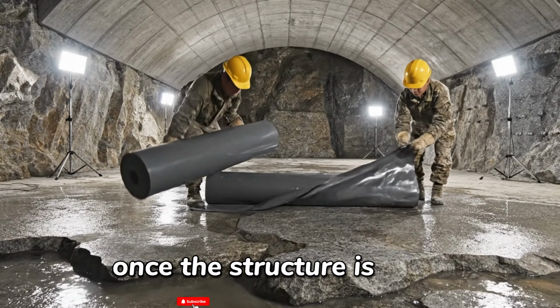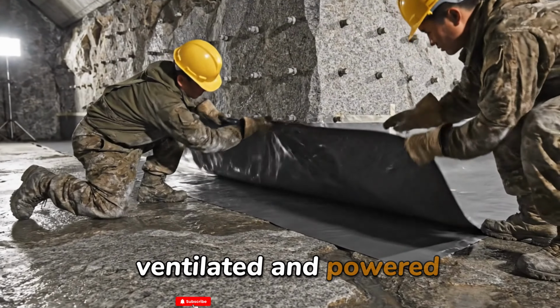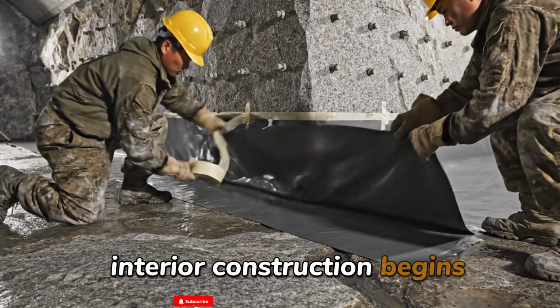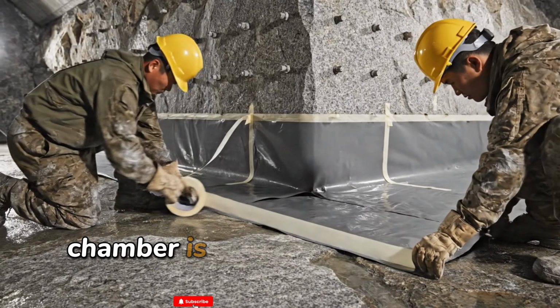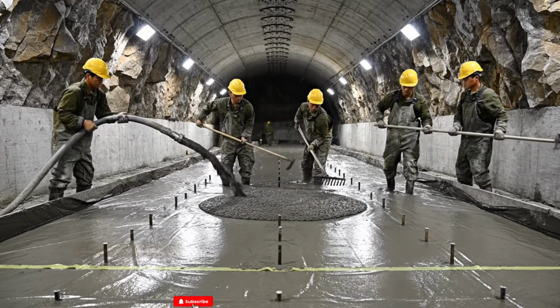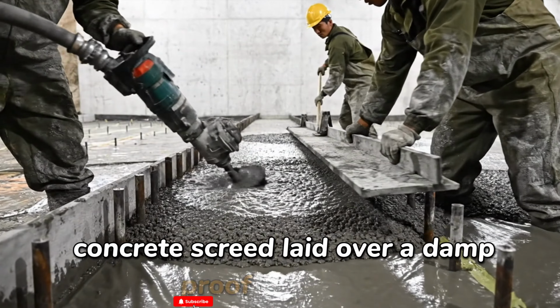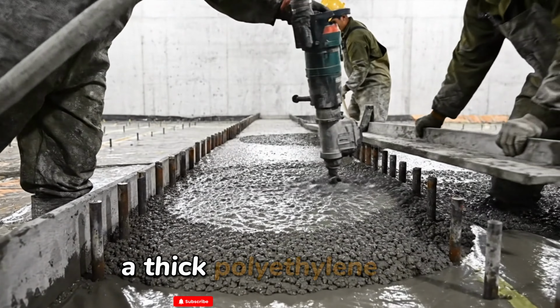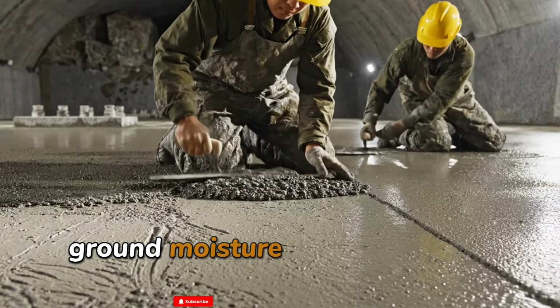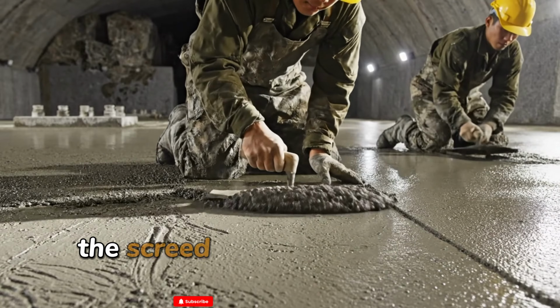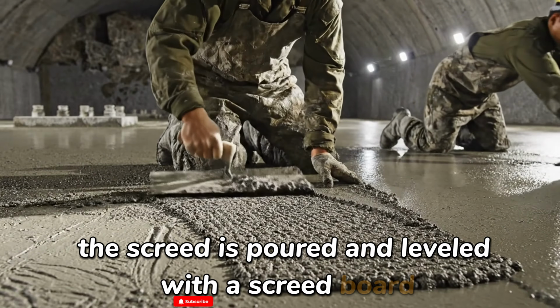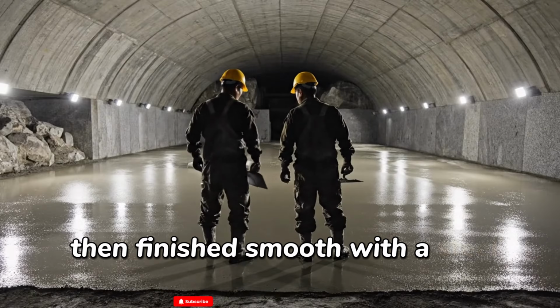Once the structure is sealed, ventilated, and powered, interior construction begins. The rock floor of each chamber is first leveled with a 100 mm concrete screed laid over a damp-proof membrane, a thick polyethylene sheet that prevents ground moisture from wicking up through the floor. The screed is poured and leveled with a screed board, then finished smooth with a steel float trowel.